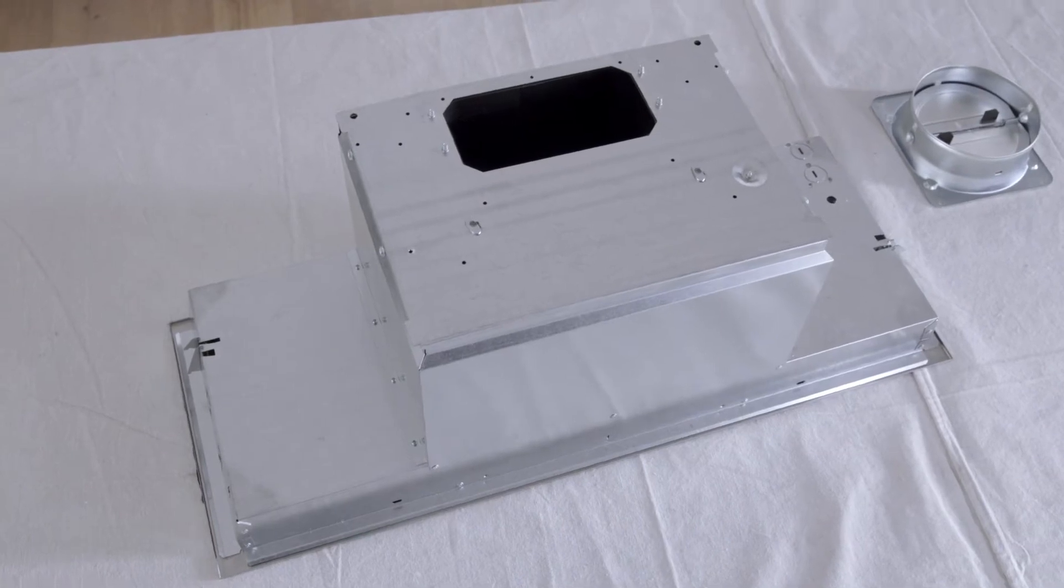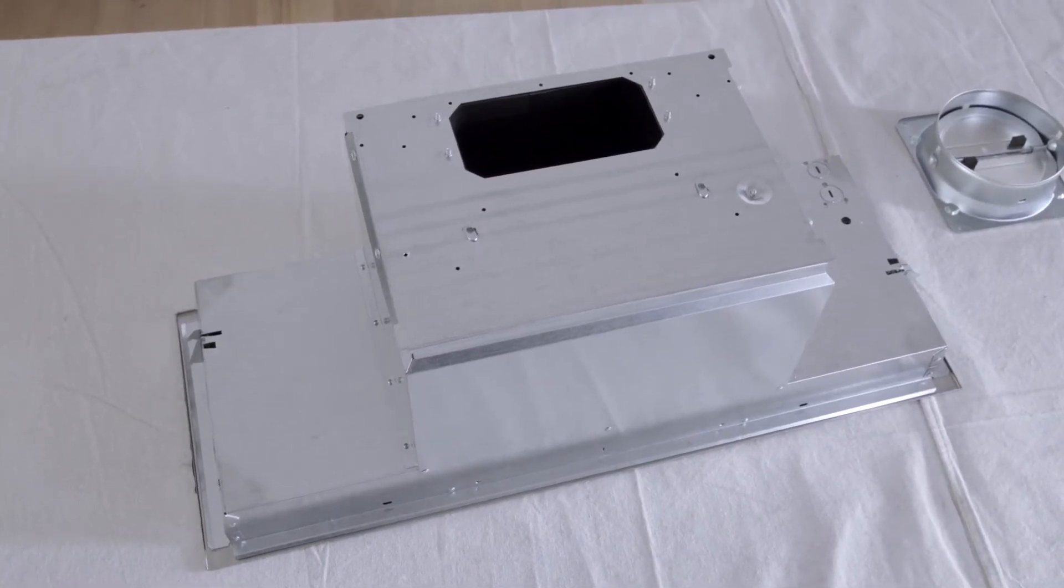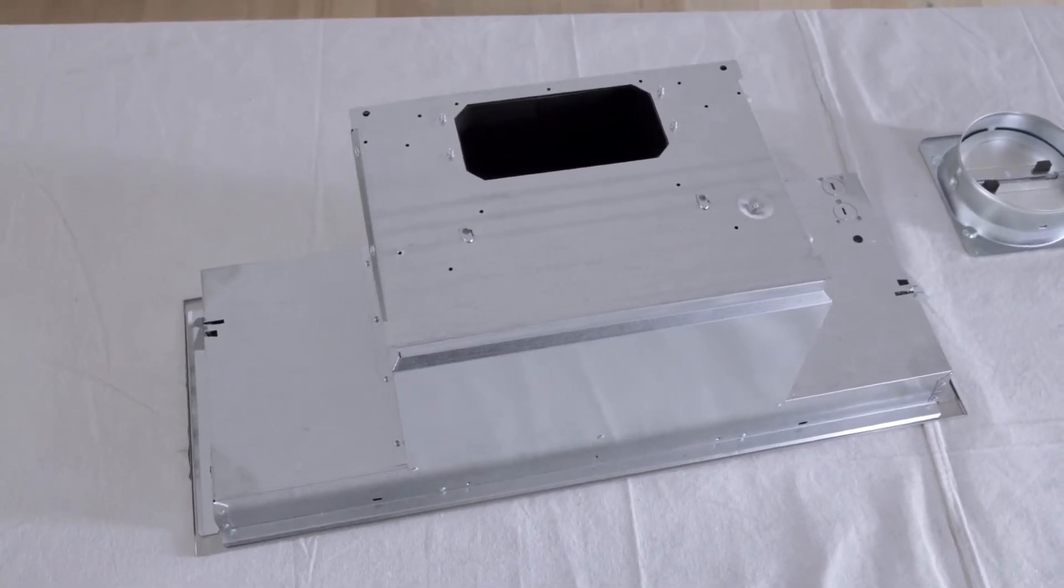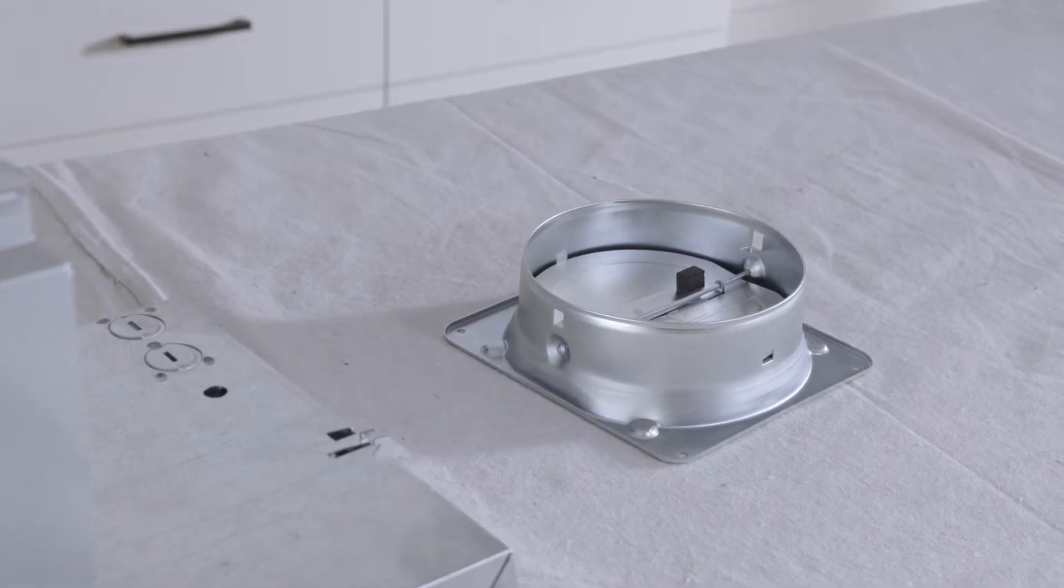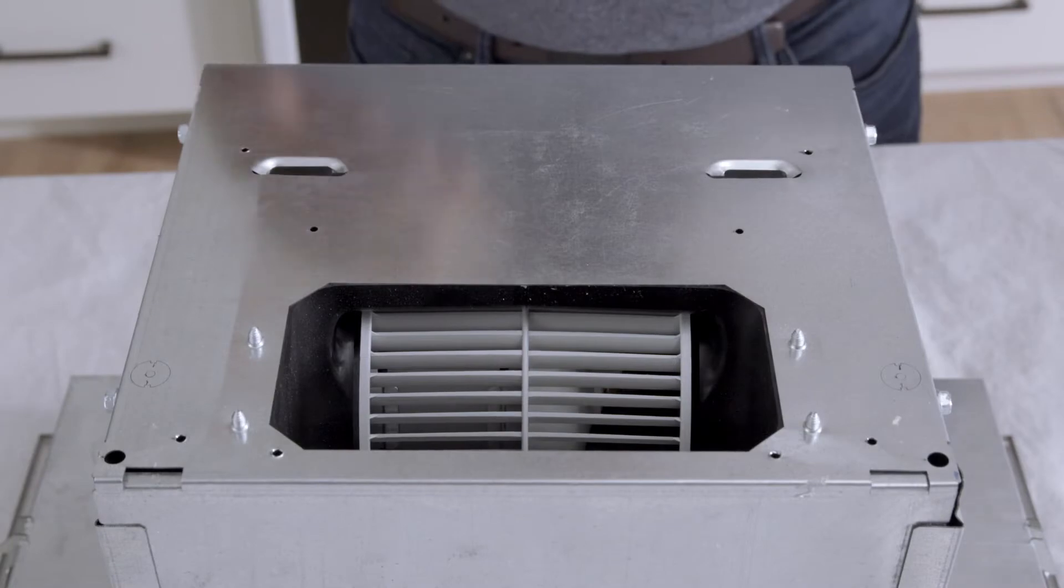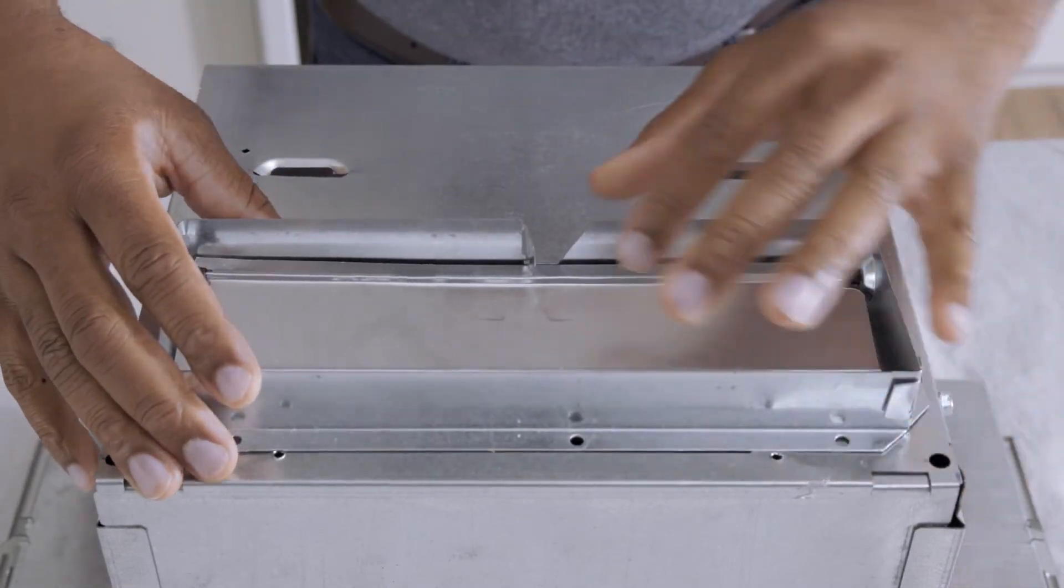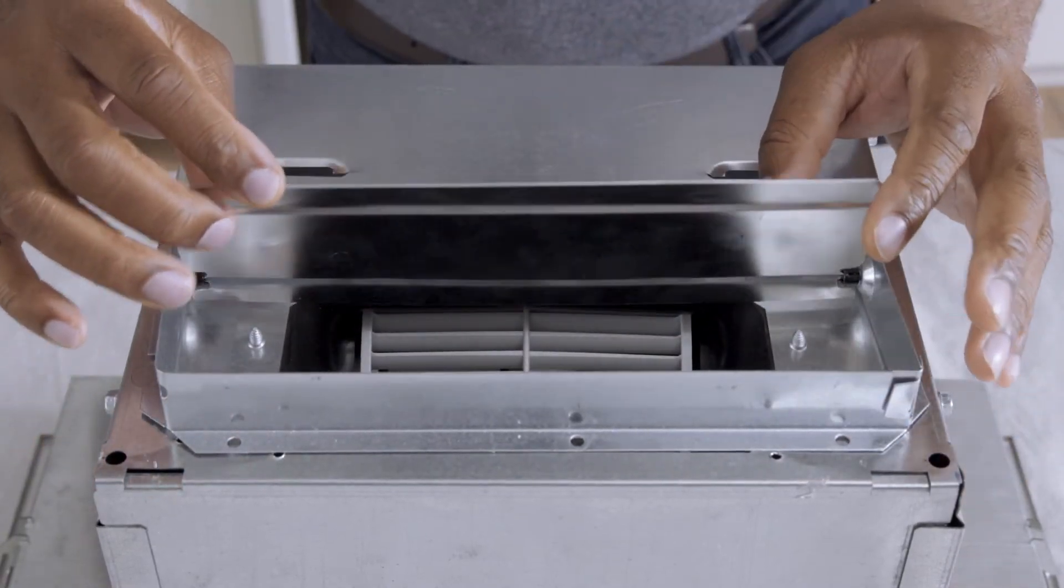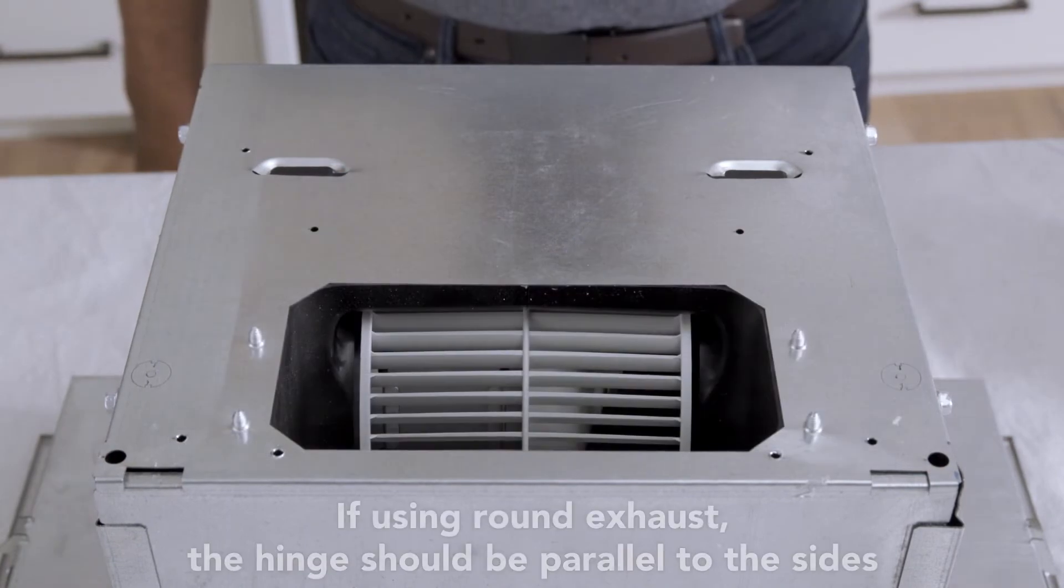The unit comes set up for vertical exhaust out of the box. For a vertical exhaust installation using round ducting, attach the appropriate damper assembly. Note the hinge position. If using the rectangular damper, the damper hinge must be toward the front of the unit.